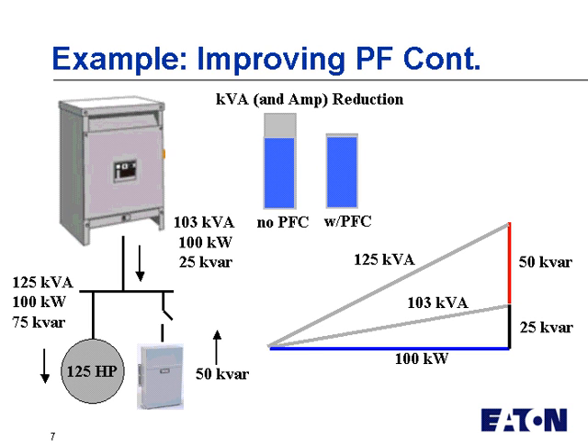For example, the motor on the left requires 125 kVA, or 100 kilowatts and 75 kVAR, to operate. Now, that could totally come from the utility transformer just north of that, or part of it could come from that capacitor just to the right of that. So 50 kVAR comes from the capacitor in this case to provide part of the 75 kVAR, and then the additional 25 kVAR comes from the utility source. And you can see with the blue and the gray scale there that it's a significant reduction in kVA and also amps back through the system. So you can appreciate the actual kilowatt or kVAR savings, kVA savings, and actual amp savings.